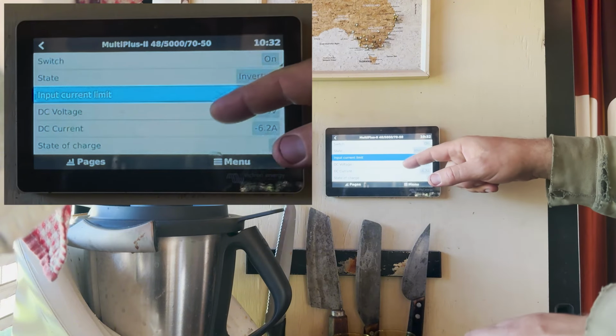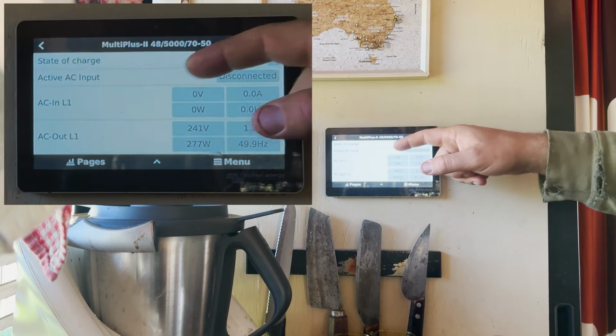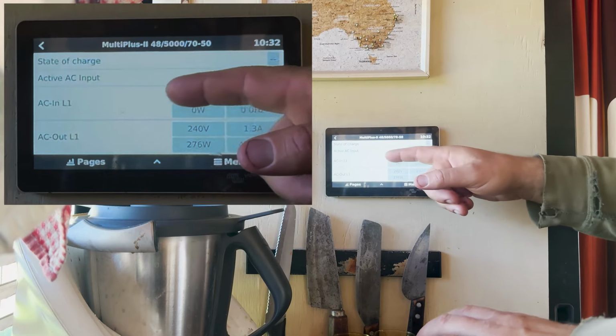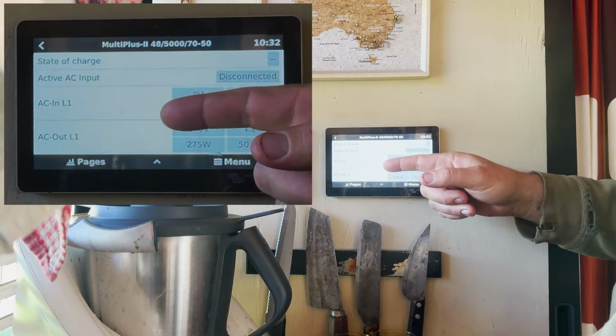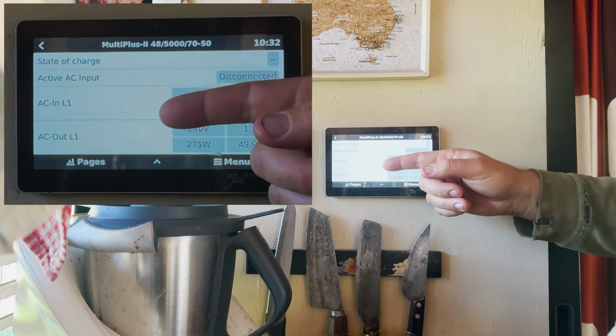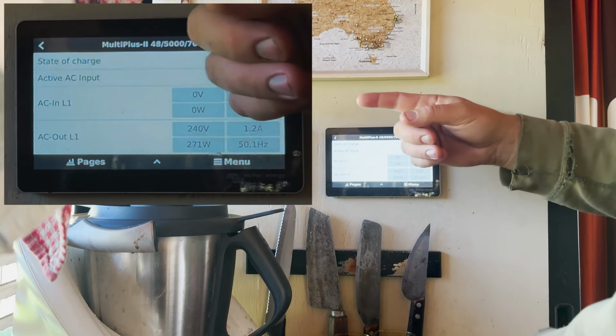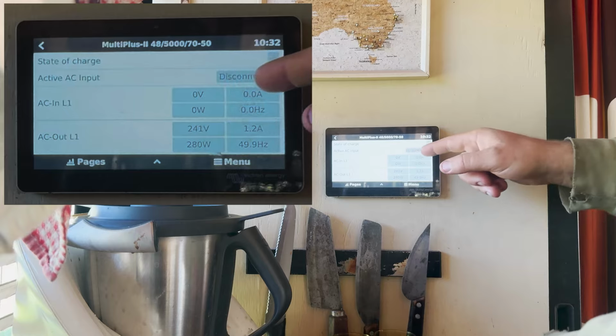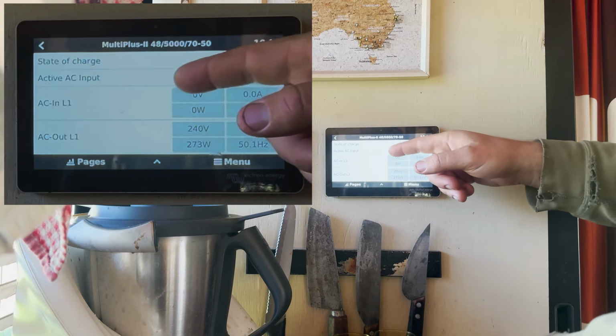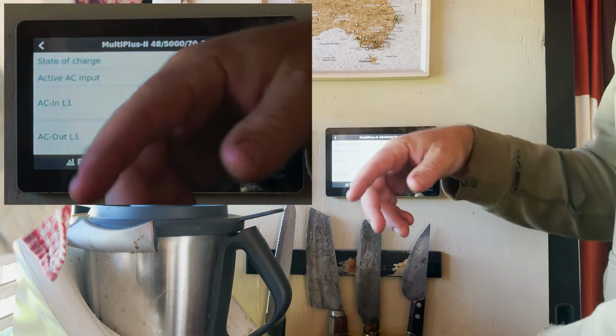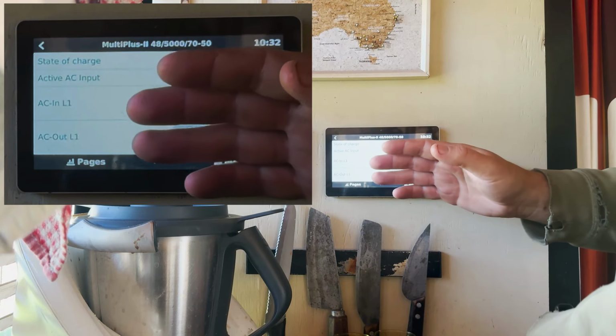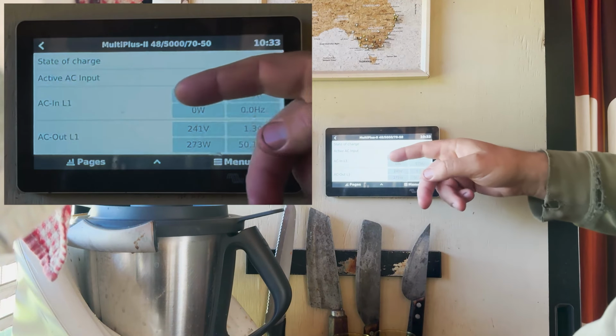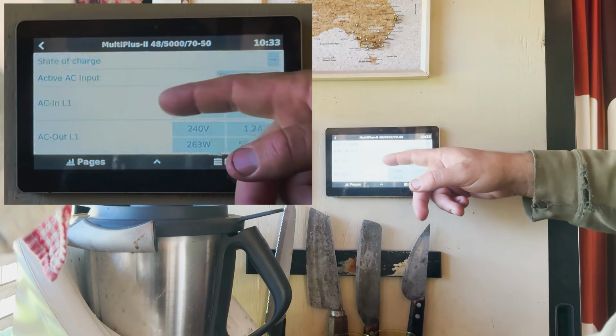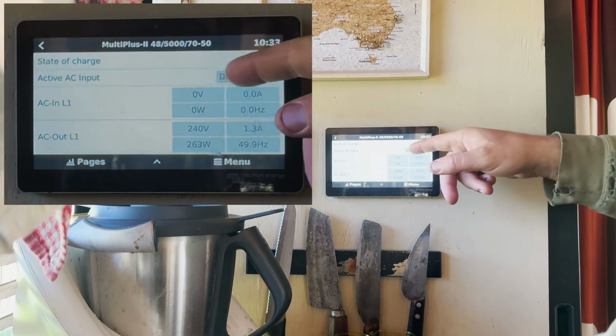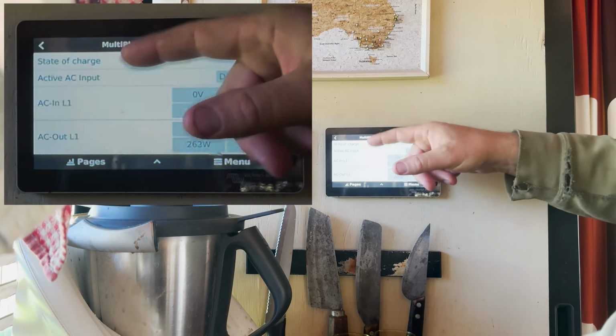Under the MultiPlus, we can see the AC in, which shows us voltage, amps, watts and hertz on the incoming power. Sometimes when we plug it in, we see this rise up with 0 amps, 0 watts, and then it waits a minute before connecting. They're waiting for the sine waves to sync, and then they'll connect. So that's a handy thing to look for when connecting, just to see if the MultiPlus itself is seeing the voltage.